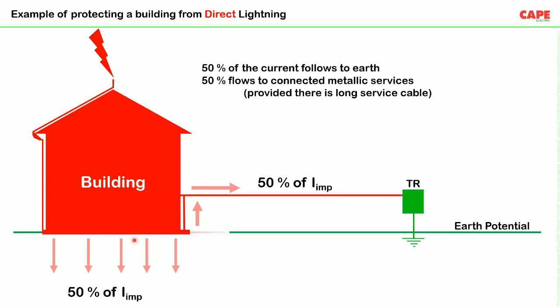So 50% of the current is diverted to the power line or to the connected services, provided there is a long connected service line. Let's say, for example, if the line is 200 meters or 300 meters, then a large amount of current flows through this particular line. But imagine a situation where the transformer is very close to your equipment, very close to your building. Under that condition, 50% current may not flow through the LV connected service, because there we have to make a separate calculation. We will talk about it probably in part 2 of this seminar.